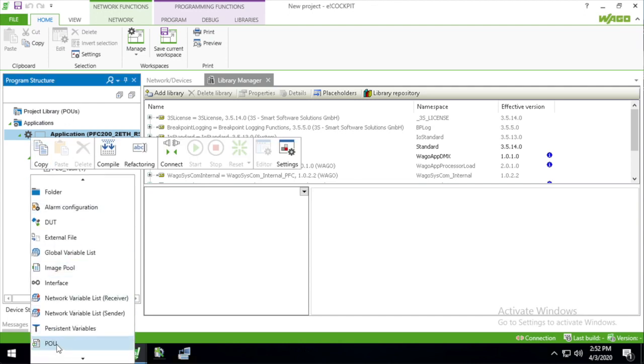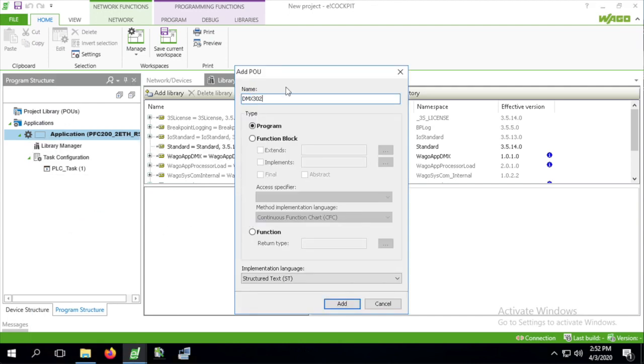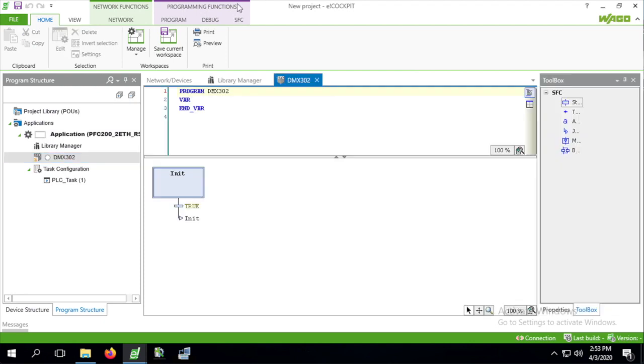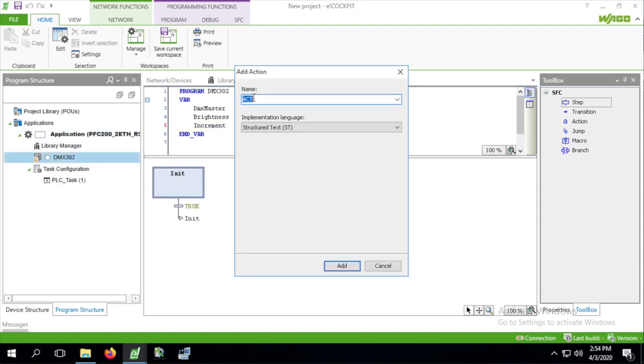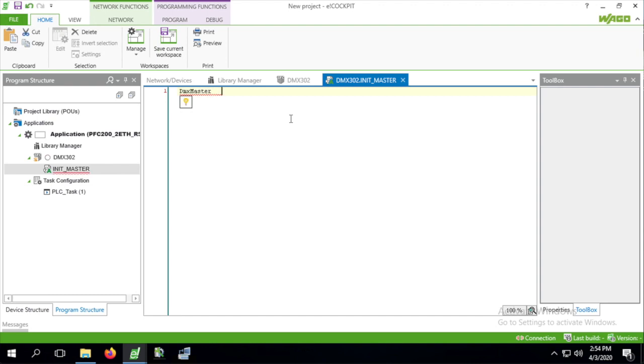We start by adding the program POU in sequential function chart language as the main program. I'm declaring the DMX master function block along with two integer values for brightness and brightness increment. Next we create a new action to initialize the DMX master with the serial module interface, and we also specify the DMX universe number which is 1 and the number of channels to control, also 1 in this case.